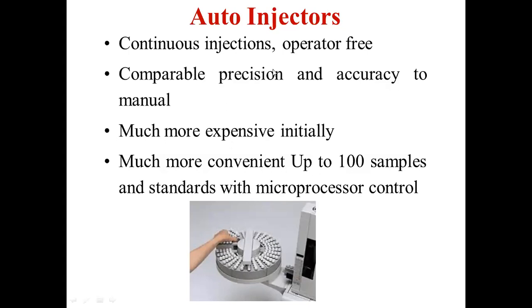So continuous injectors can also be used. They are operator free. As I told you, we can adjust the time interval for choosing the sample at different time intervals. Comparable precision and accuracy can be expected. Of course, this is highly automated, much more expensive, and up to 100 samples and standards can be processed, because a microprocessor control will be available here, just like the microprocessor unit you can see in the flame photometer we have in our laboratory.